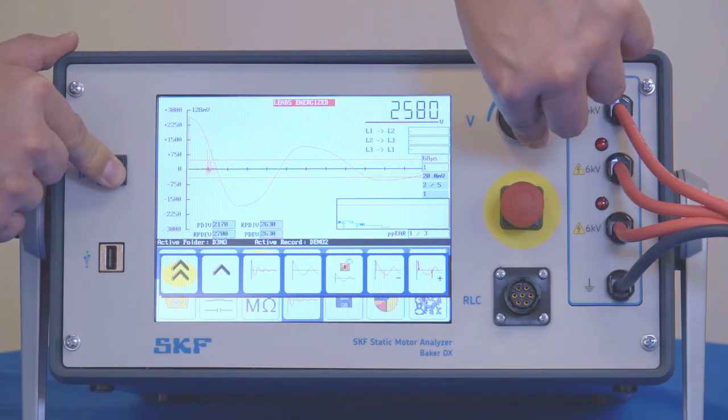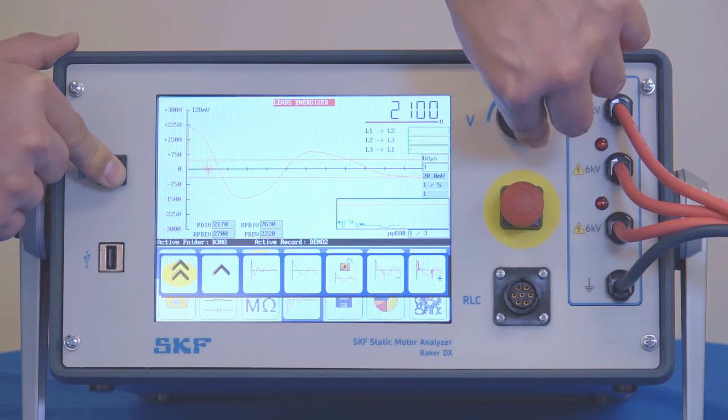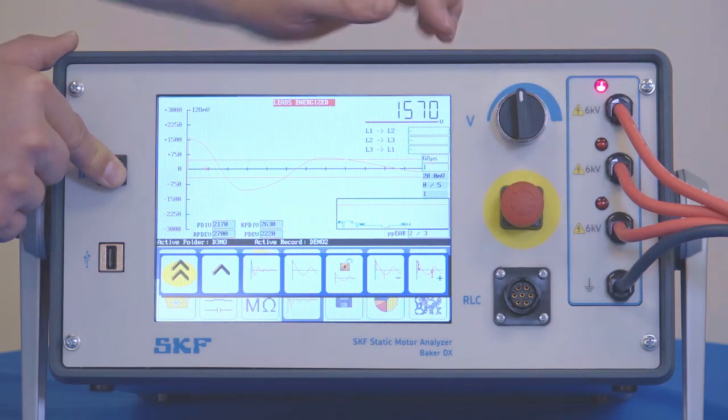As you can see immediately the extinguished voltage populated. I'm going to continue to ramp until that partial discharge extinguished voltage goes completely away and the voltage is at a minimum. Then we can stop the test.